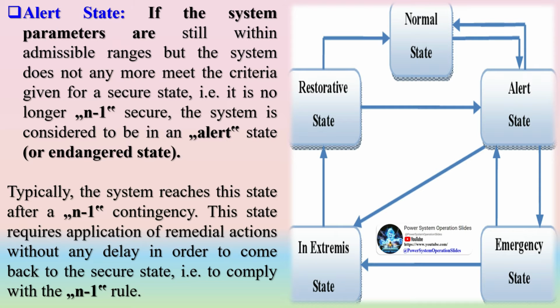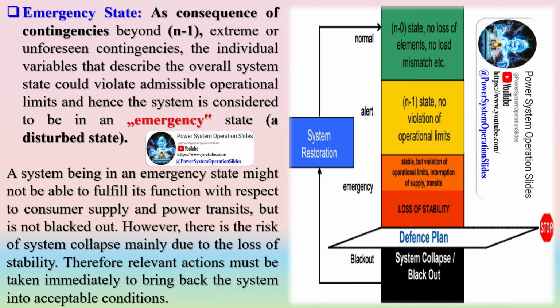Classification of system states and contingencies. For purposes of analyzing power system security, it is first of all helpful to conceptually classify the system operating conditions into system states. Normal state: all system variables are within the normal range and no equipment is being overloaded. The system operates in a secure manner and is able to withstand predefined contingencies without violating any of the constraints. Alert state: if the system parameters are still within admissible ranges but the system does not anymore meet the criteria given for a secure state, i.e. it is no longer N-1 secure, the system is considered to be in an alert state or endangered state.